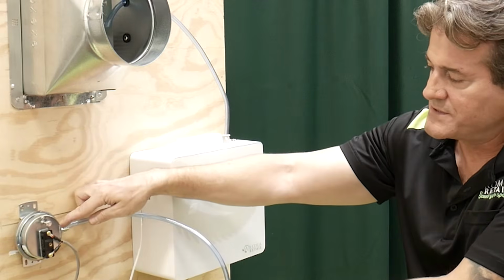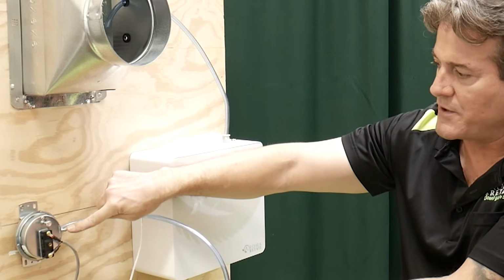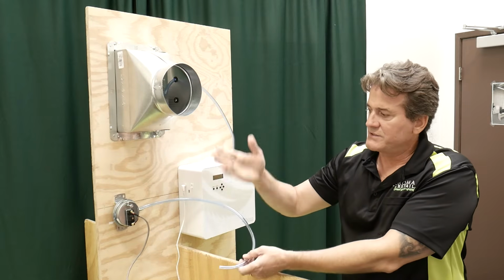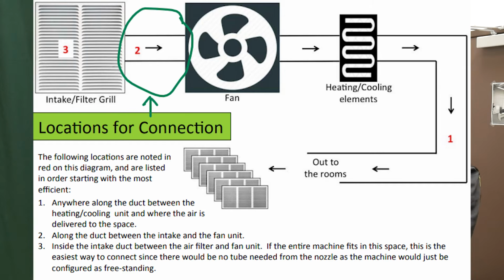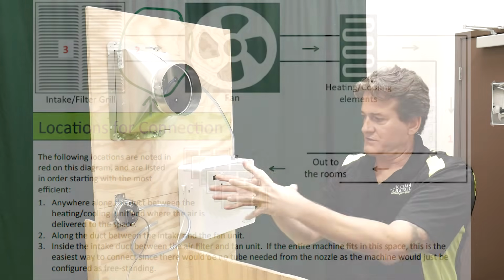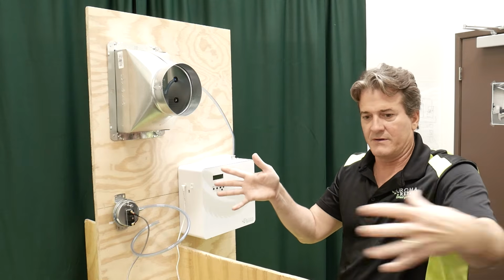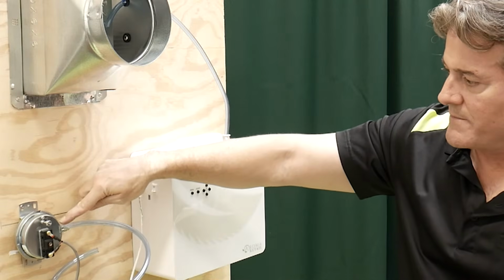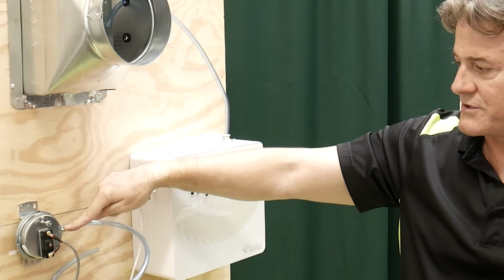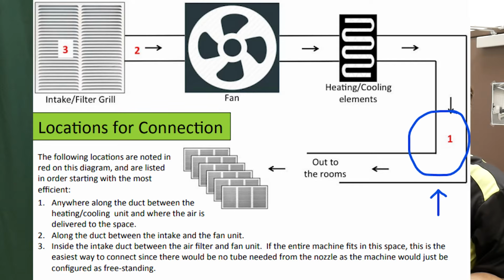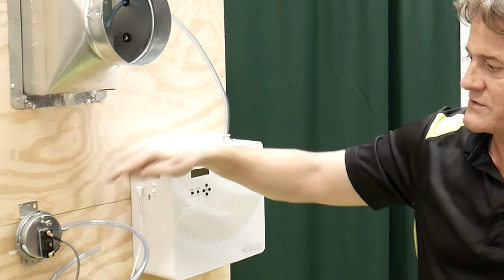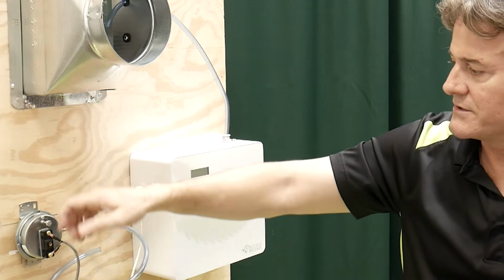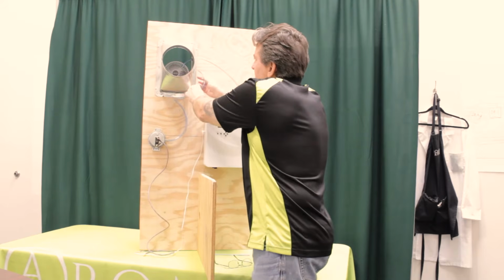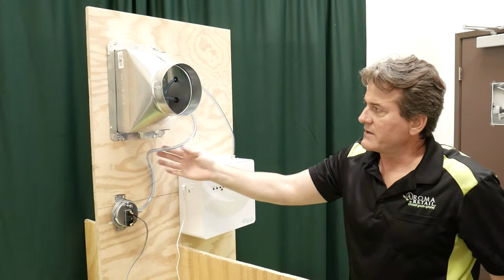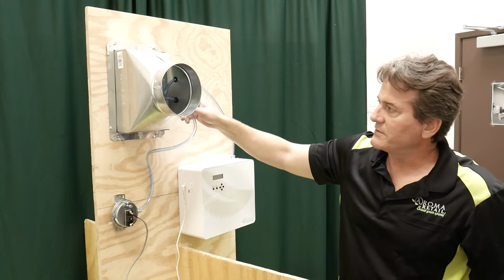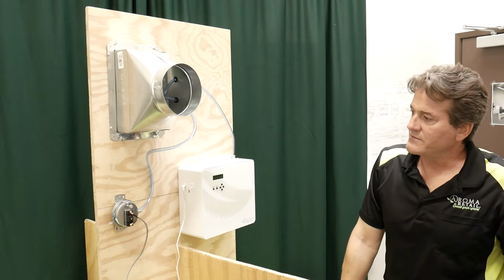The air switch has 2 barbs. This one that's facing me is the low pressure barb. So if I were putting this tube between your filter and your fan for your air conditioner, well, that's a low pressure zone because it's sucking air from the air filter and pulling it through the fan. That's low pressure. So I'm going to want my hose to be on this barb to sense low pressure. Here I'm just putting it in the same duct after the fan, right along with the fragrance tube. So I'm going to put it on the high pressure barb so it senses high pressure. I've already trimmed this tube a bit, but this one doesn't get condensation, so I'm not concerned about any bellies or anything. I just need to get that hose in there a couple of inches so it can sense the change of air pressure when the fan comes on.